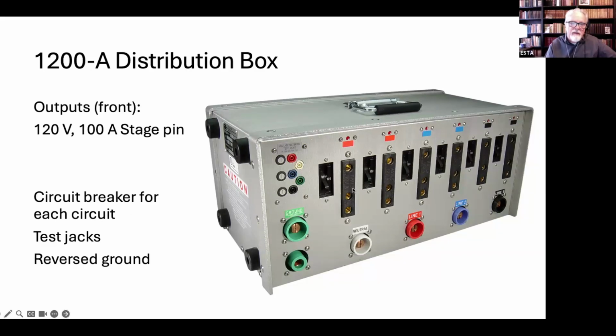outlets. This particular box also has these test jacks in the left corner. Test jacks allow you to plug a voltage meter or a multimeter into the system at this point. It tells you what your voltage is. Tells you if your frequency is on target. Sometimes if a generator gets out of whack, the frequency will be off. And sometimes if you have a very, very long cable run, if there's a problem, you could have a low voltage at the loads. So that's what that's for.